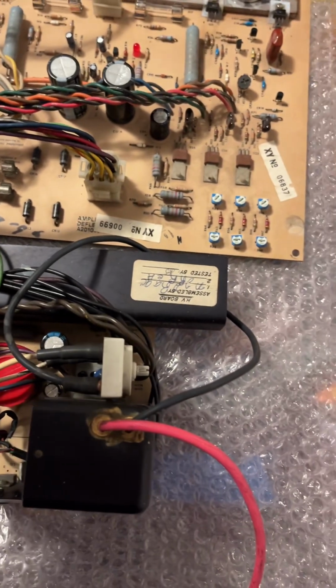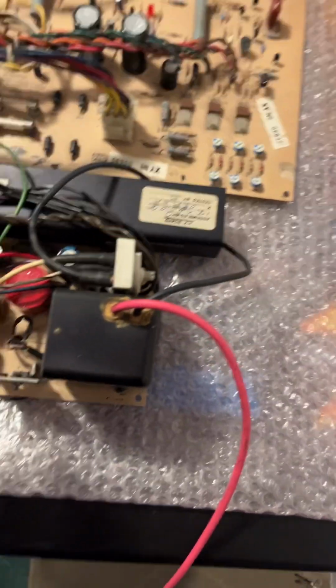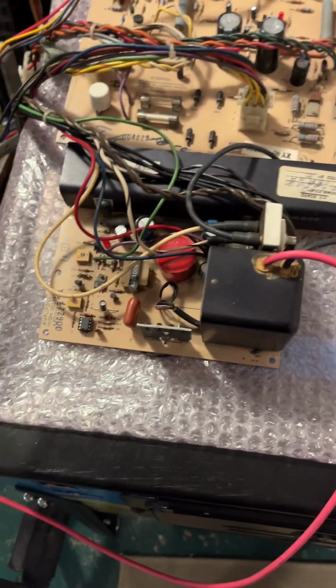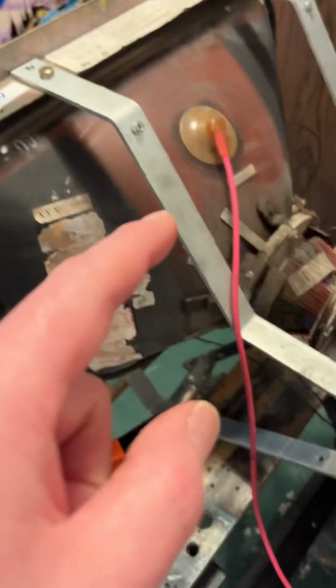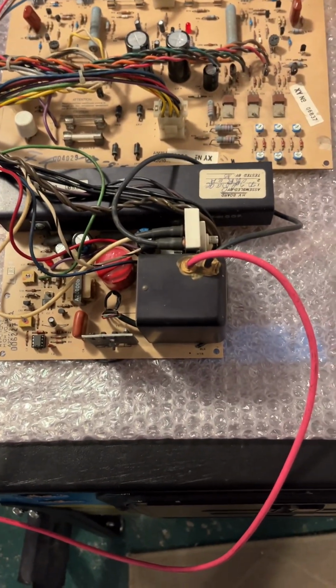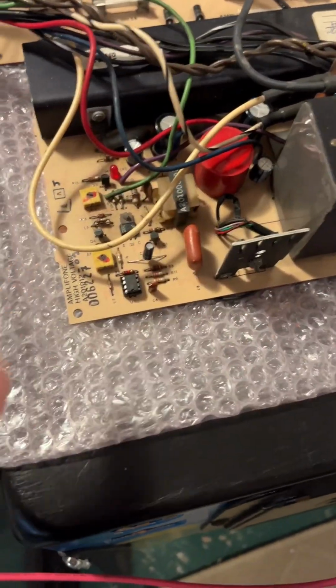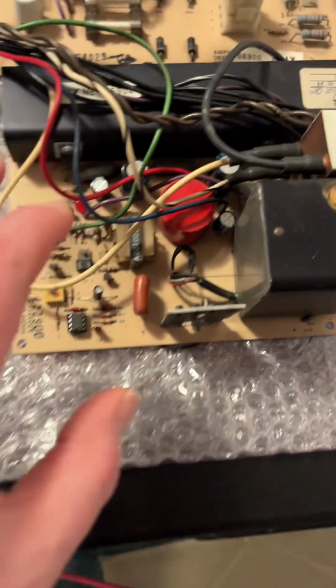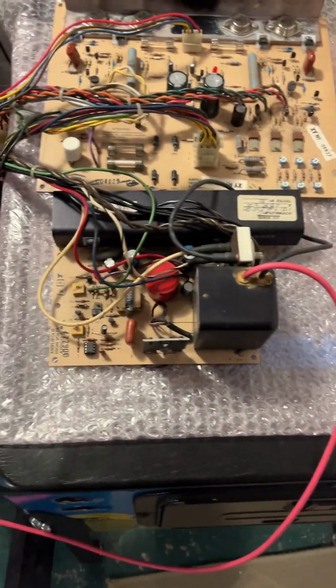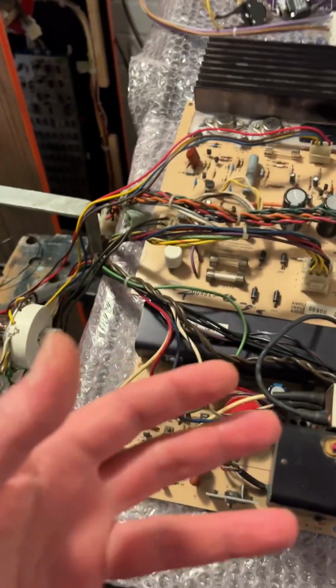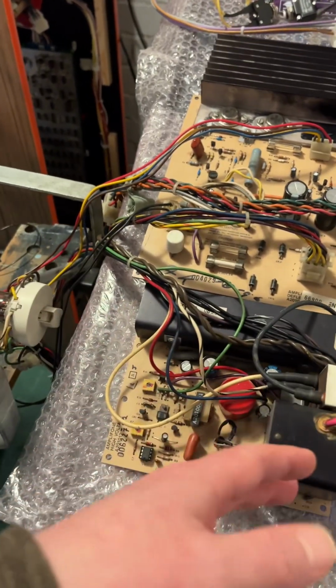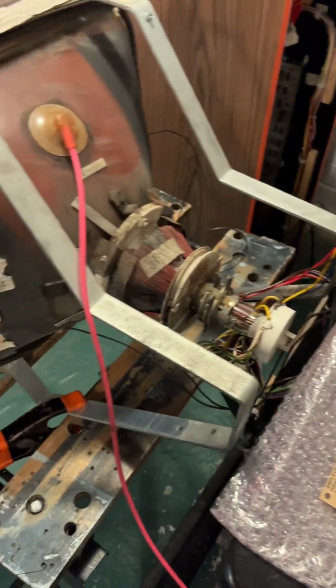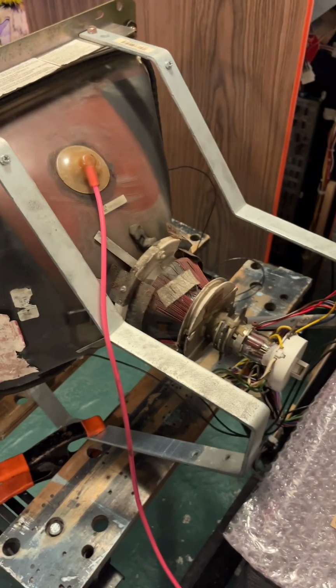That creates the voltage, which is then output through this connector to the high voltage board. So it rectifies and sends DC voltage to this high voltage board, which then takes that DC voltage and creates the high voltage needed for the tube. So it's all a bit kind of crazy. Because on this high voltage board, there's two regulators. There's a plus 24 and a minus 24 regulator, and then whatever all this gubbins does, which we could get into, but not for this video, takes those voltages and makes the signals and voltages needed for the flyback to create all the high voltage, which is up at like 20,000 volts.